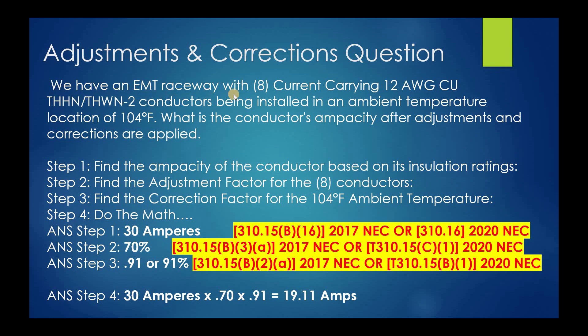So let's look at the question. We have an EMT raceway with eight current-carrying conductors. They're 12 gauge copper, THHN/THWN-2. That's important because since it has a dash two, it doesn't matter whether it's wet or dry — we pull our starting ampacity from the highest rated temperature of that insulation, which is 90 degrees C. The conductors are being installed in an ambient temperature of 104 degrees Fahrenheit. What is the conductor's ampacity after adjustment and corrections are applied?